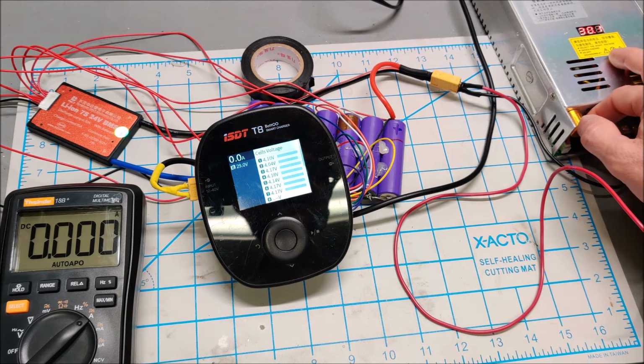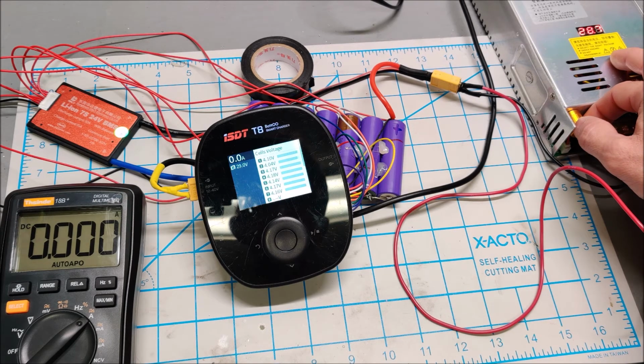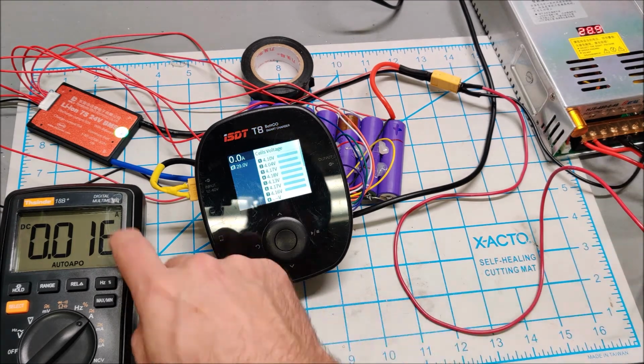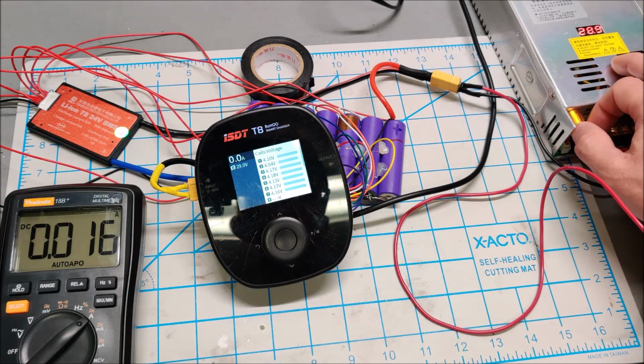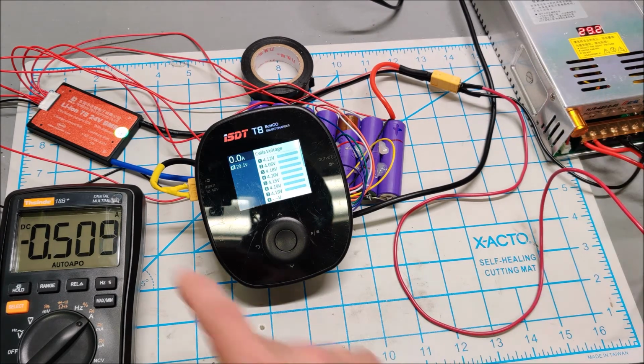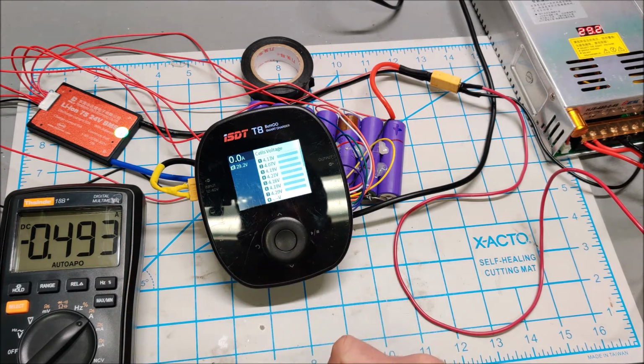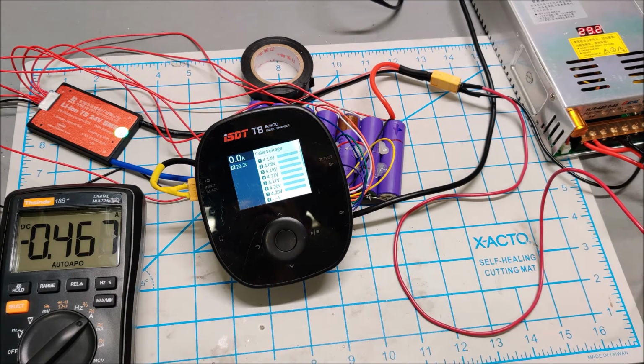Now if we bring that voltage down a little bit, 29.1... oh, too high, this is very sensitive. There we go, once you bring the voltage down low enough, the BMS turns back on. If I just nudge this up a hair, 29.2, and now we're pulling half an amp to charge these cells. So the BMS does exactly what it's supposed to on the top end, watching for overvoltage and turning off the current.